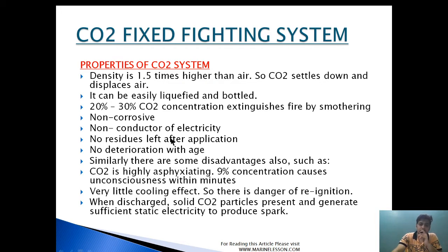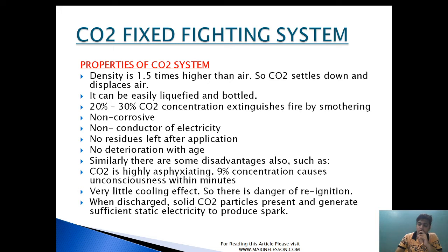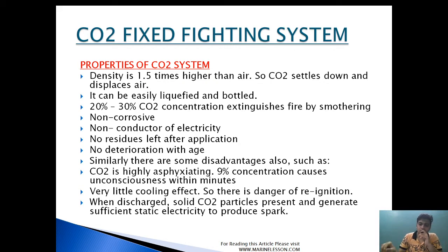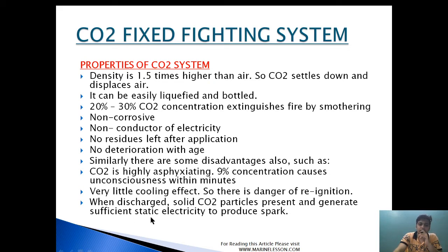Some disadvantages: CO2 is highly asphyxiating — a 9 percent concentration causes unconsciousness within minutes. It has very little cooling effect, which creates a danger of re-ignition. CO2 also extinguishes fire by smothering as well as by some cooling action. When discharging, solid CO2 particles generate sufficient static electricity to produce a spark, and therefore CO2 lines should be properly grounded — a very important point.